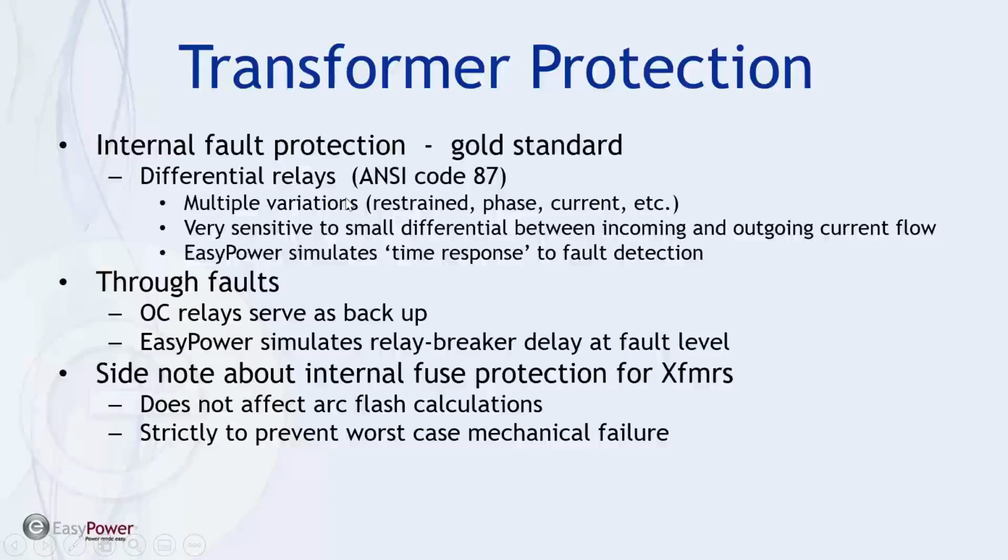will be the level that triggers the relay operation, and that can be resolved much more finely than the total overcurrent or even instantaneous overcurrent that we would sense through a CT. We'll talk a little bit more about that at the tail end of this. What I'm going to focus on first are the through faults.